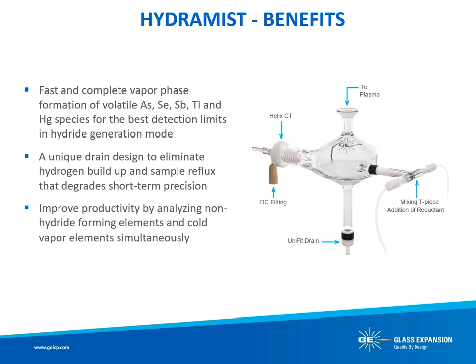The design of the Hydramist spray chamber is based upon Glass Expansion's industry-standard cyclonic spray chamber, giving excellent sensitivity and short-term analytical precision with fast washout. The Hydramist features a secondary inlet port that mixes the aerosolized sample and liquid reductant inside the spray chamber for rapid conversion of arsenic, selenium, antimony, thallium, and mercury analytes into volatile hydride species. The unique drain design ensures fast, complete removal of waste from the spray chamber, eliminating excess hydrogen buildup that causes sample reflux and degrades analytical precision.